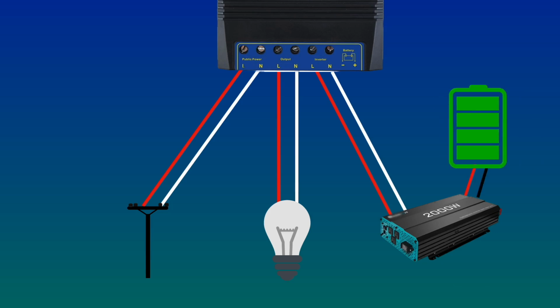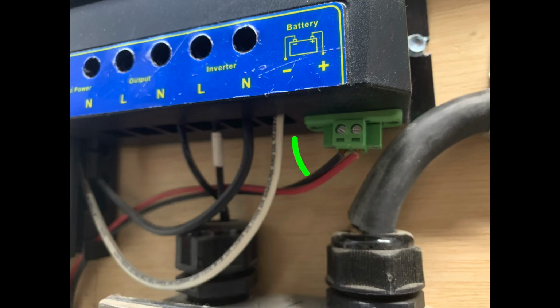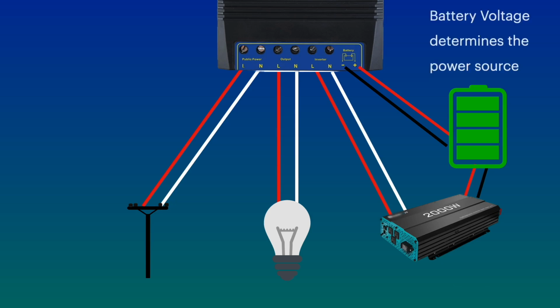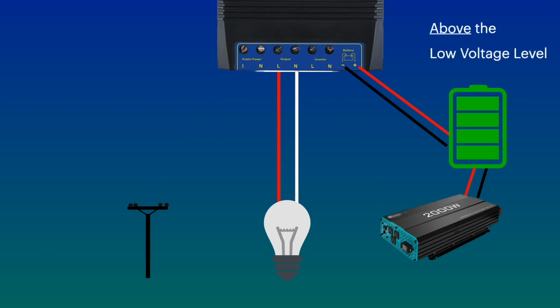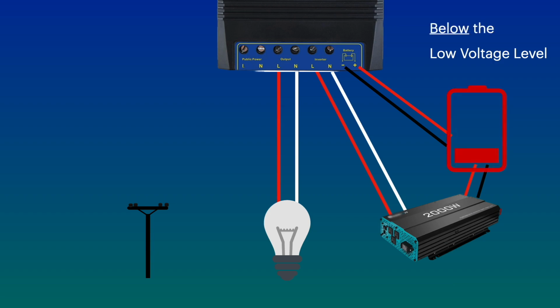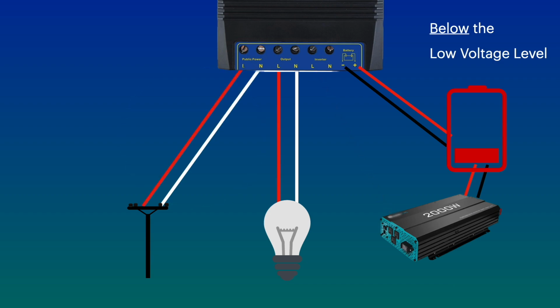Now, the battery that you have connected to your inverter, you will also take two leads off of that battery and connect them right here underneath. Now, this will supply the power that runs this unit. And the voltage of this battery determines the power source. If the battery voltage is above what's called the low voltage level, then you will be running on the inverter. If, however, you run the battery down below the low voltage level, the automatic transfer switch will disconnect from the inverter and connect you to the grid, therefore protecting the battery.